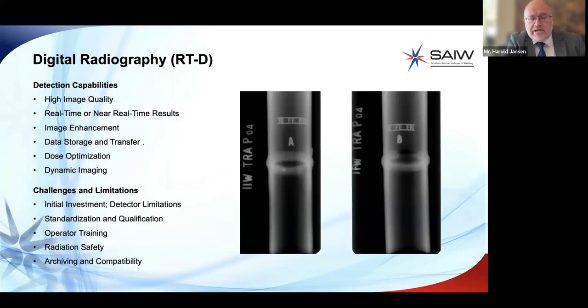Some of the detection capabilities. The key strengths of digital radiography include the high image quality. In other words, the digital systems can produce images with fine resolution and high contrast sensitivity. The digital tools also allow for zooming, filtering, contrast adjustment, and defect measurement without rescanning. So that refers to the image enhancement. And then also the dose optimization. In other words, digital detectors often require less radiation exposure than film for equivalent image quality, hence actually improving the safety of the inspection process itself.